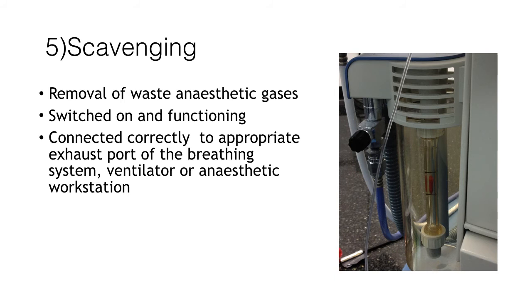Scavenging is the removal of waste anaesthetic gases. It is important to ensure that this is correctly working as there are safe limits set out by the Control of Substances Hazardous to Health regarding how much exposure there should be to anaesthetic gases. The scavenging is often a clear tubing which is attached into the wall. It should be switched on and functioning, and connected correctly to the appropriate exhaust port of the breathing system and the ventilator.